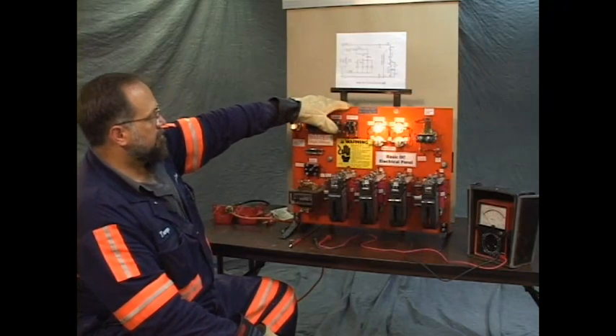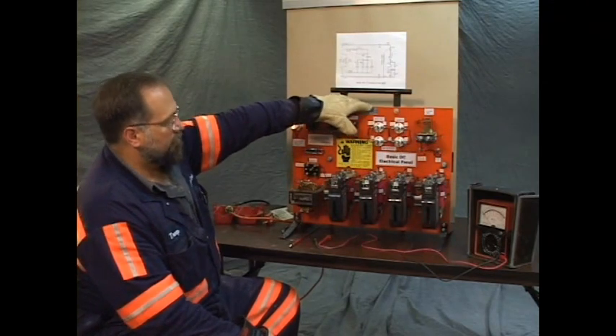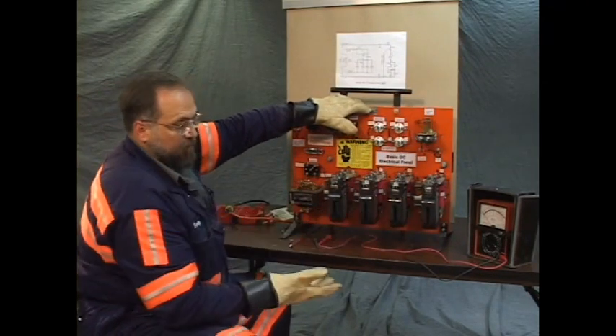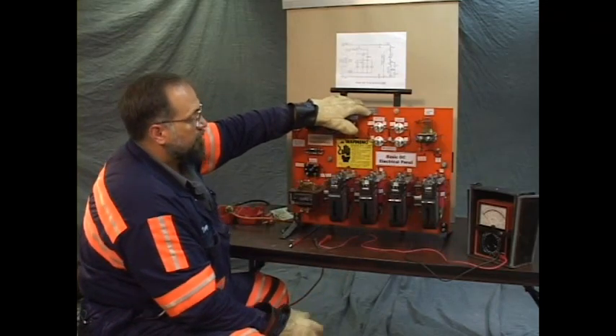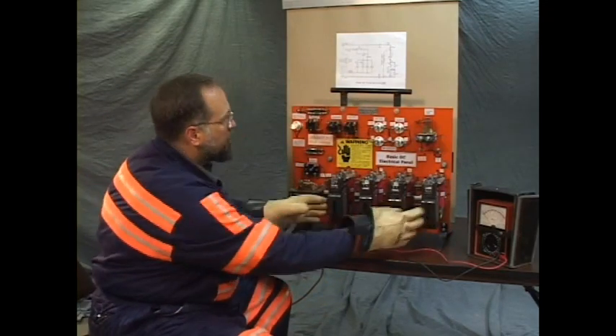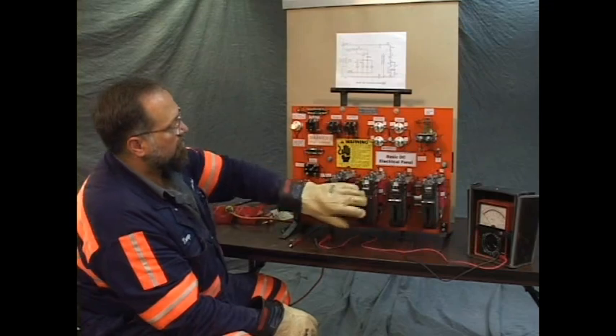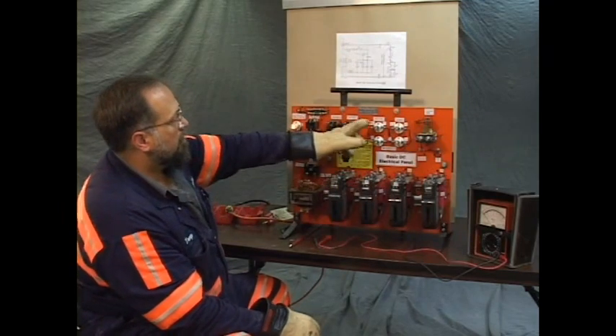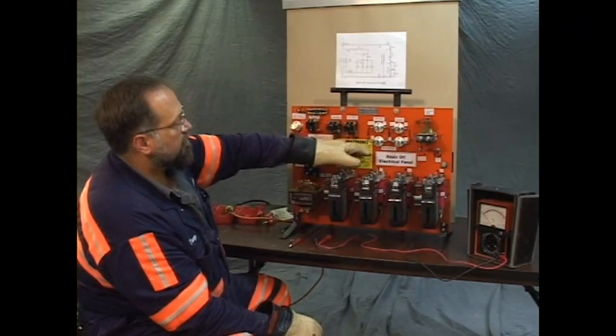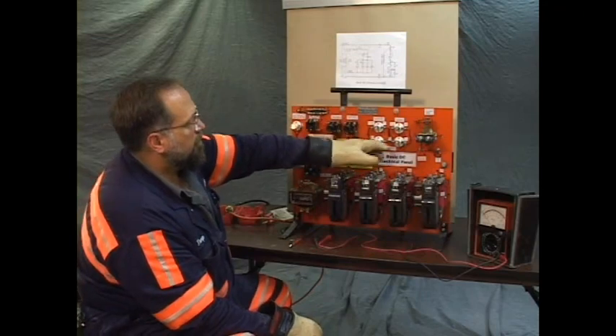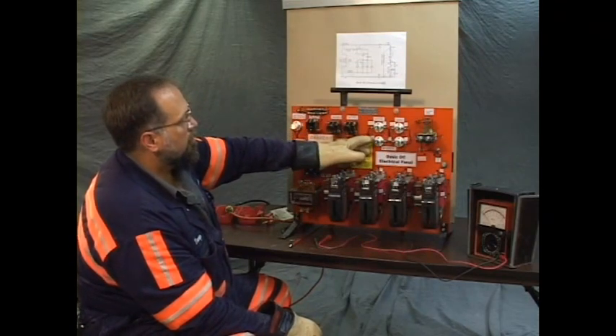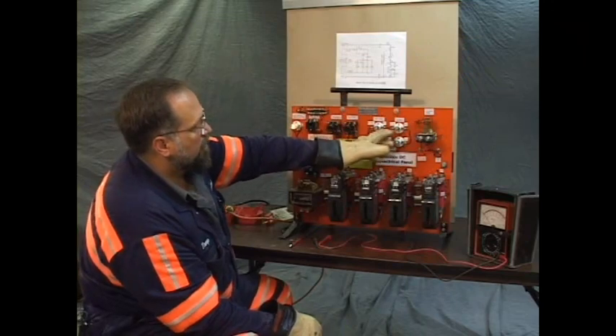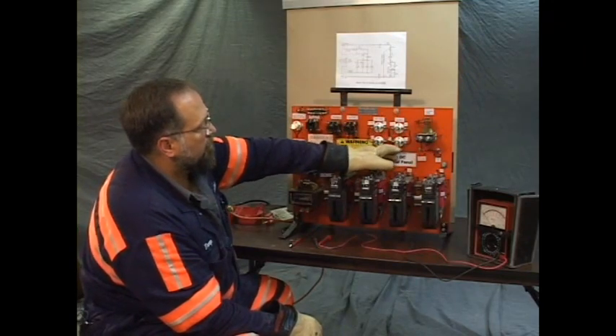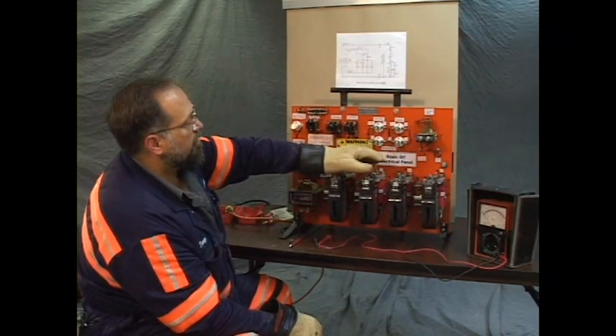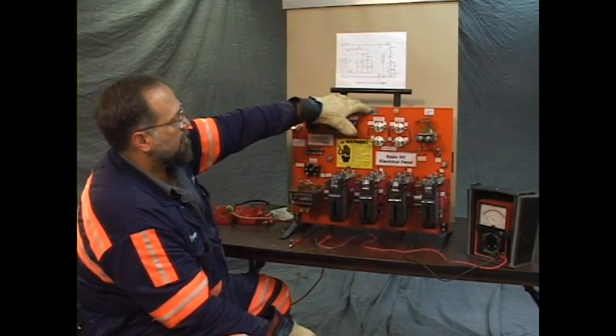Click, click, click. You have 4 contactors, but you'll note you only have 3 clicks because M1 and M2 close simultaneously, then 1A and then 2A. All 4 lights light up first, and these 3 are dim, and R1, R2 light will go off. These 2 will become brighter. R2 and R3 will go off, and this one will be very bright. Watch close. Watch the lights.